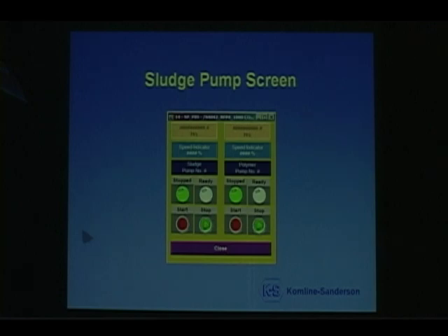Sludge pump screen. When you touch the sludge pump or the polymer pump picture on the overview screen, this screen will pop up, and it has the hour meters up top. You've got the speed indicators. When you touch those, another screen will pop up and allow you to change them. For the sludge, it'll allow you to change the flow rate. On the polymer, it'll give you the percent speed of the pump. And it's got the indicator lights, as the other ones did, and your start-stop functions.